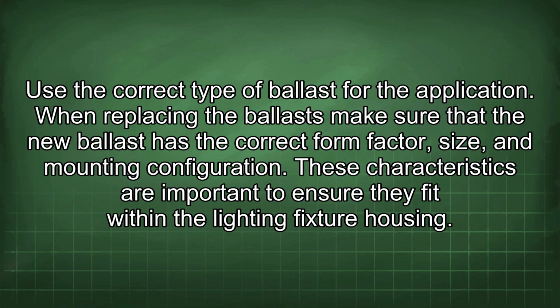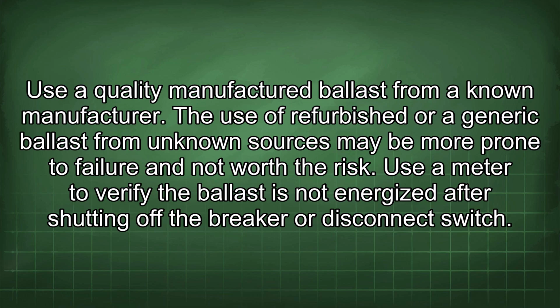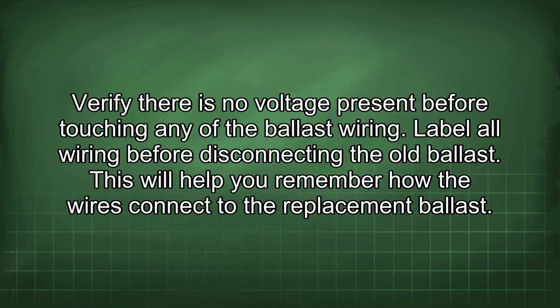When replacing the ballast, make sure that the new ballast has the correct form factor, size, and mounting configuration. These characteristics are important to ensure they fit within the lighting fixture housing. Use a quality manufactured ballast from a known manufacturer. The use of refurbished or generic ballast from unknown sources may be more prone to failure and not worth the risk. Use a meter to verify the ballast is not energized after shutting off the breaker or disconnect switch. Verify there is no voltage present before touching any of the ballast wiring.